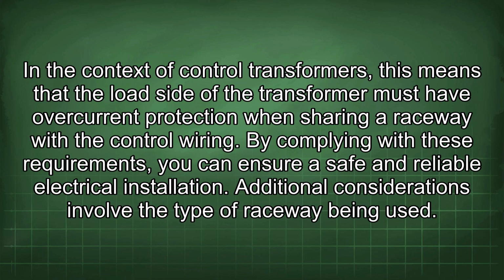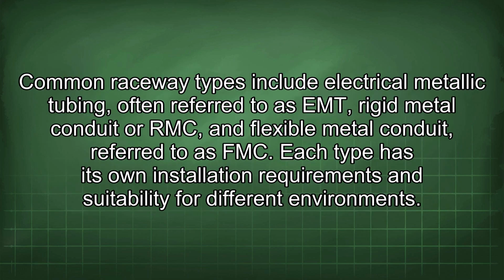In the context of control transformers, this means that the load side of the transformer must have overcurrent protection when sharing a raceway with the control wiring. By complying with these requirements, you can ensure safe and reliable electrical installation. Additional considerations involve the type of raceway being used. Common raceway types include electrical metallic tubing, often referred to as EMT, rigid metal conduit or RMC, and flexible metal conduit, referred to as FMC.